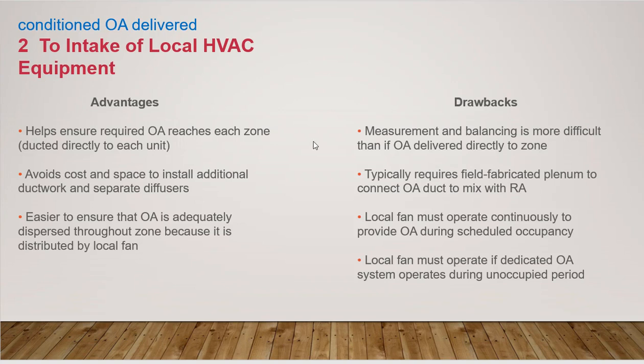Second type. We have the advantages: it helps ensure required OA reaches each zone, avoids the cost and space to install additional ductwork, and makes it easier to ensure that OA is adequately dispersed through the zone because it is distributed by the local fan. This actually was a disadvantage in type 1, but here it is an advantage because we overcome the disadvantage. The disadvantages: measurement and balancing is more difficult than if OA is delivered directly to the zone. It typically requires a field-fabricated plenum to connect OA.